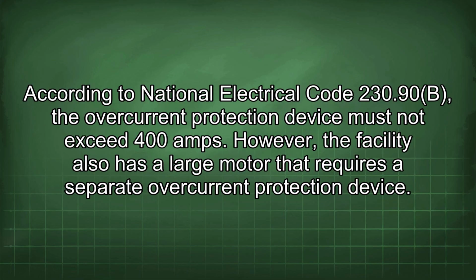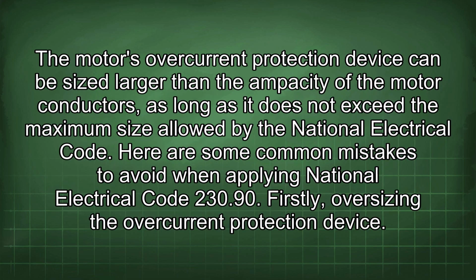Thirdly, an industrial facility has a calculated load of 400 amps. The service conductors are sized to carry 400 amps. According to National Electrical Code 230.90b, the overcurrent protection device must not exceed 400 amps. However, the facility also has a large motor that requires a separate overcurrent protection device. The motor's overcurrent protection device can be sized larger than the ampacity of the motor conductors, as long as it does not exceed the maximum size allowed by the National Electrical Code.